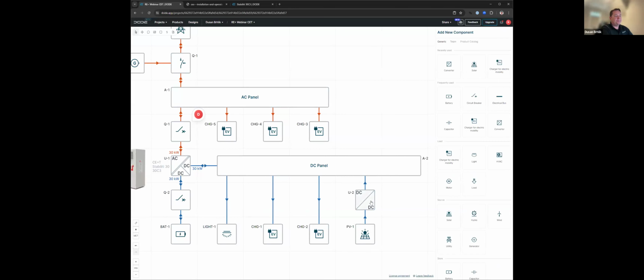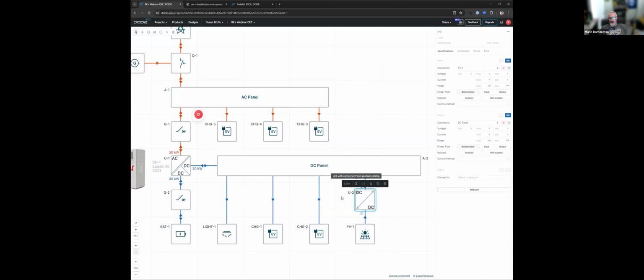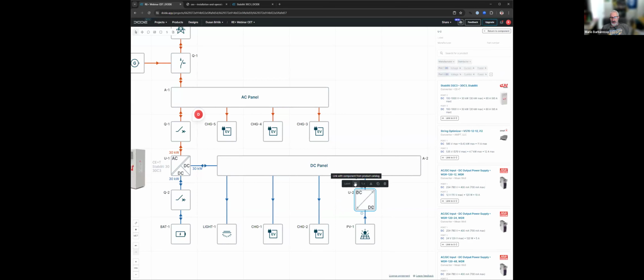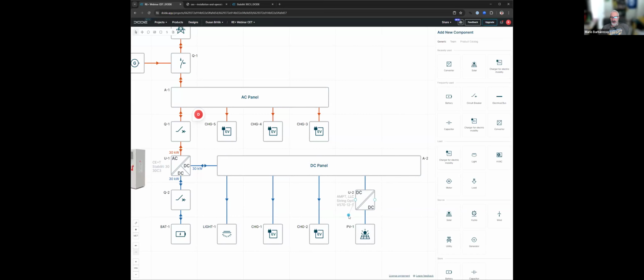That handles the MPPT optimization, because on that DC panel, it's a DC bus. This is not a place where you would add an MPPT directly. What comes out of your solar panel is variable voltage that you need to convert into a stable voltage compatible with your DC bus.